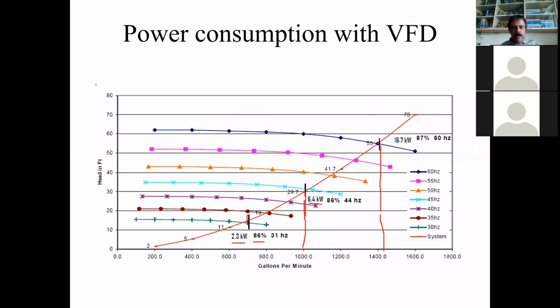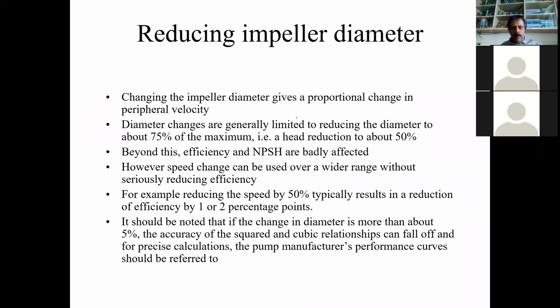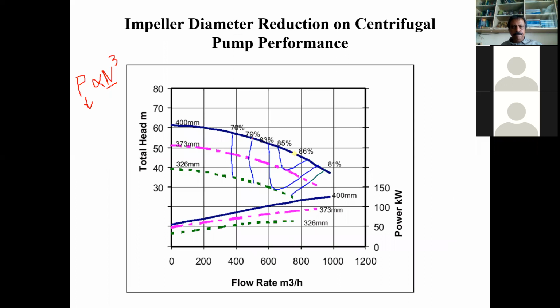And impeller diameter change is not very popular these days because VFD itself has become so cheap. Earlier, before the advent of the VFDs, most of the companies were looking at the option of impeller diameter change, but now it has been taken over by VFD, which they feel is much safer and also economical. With an impeller diameter change, as you reduce the diameter, the pump behaves like a smaller pump, just like the speed change.